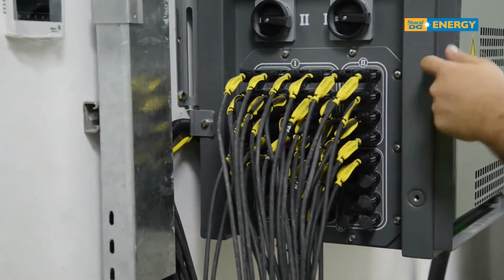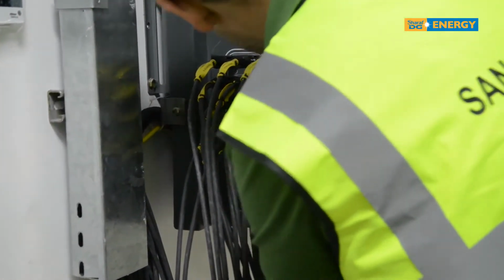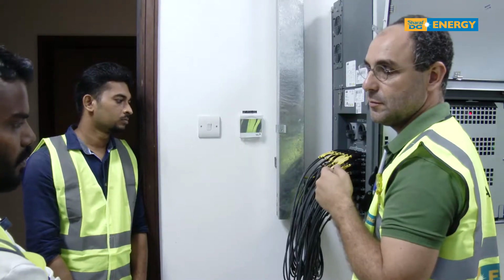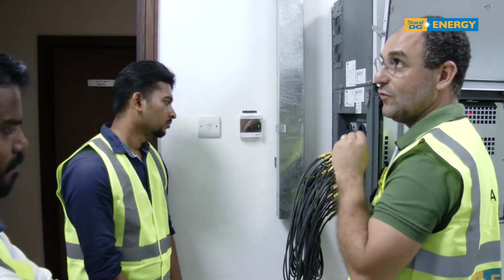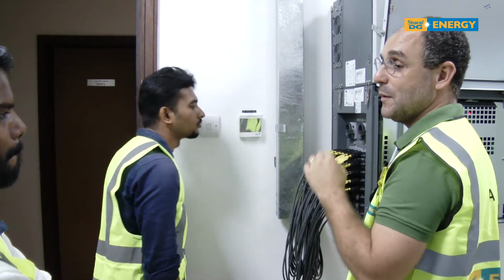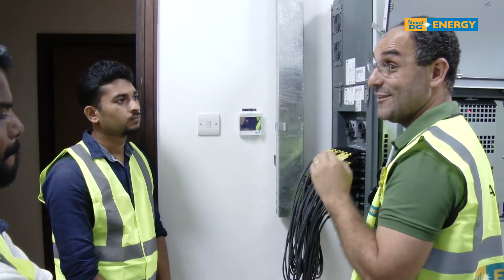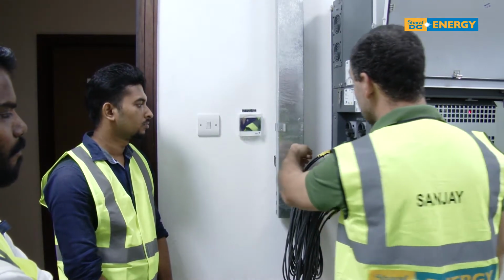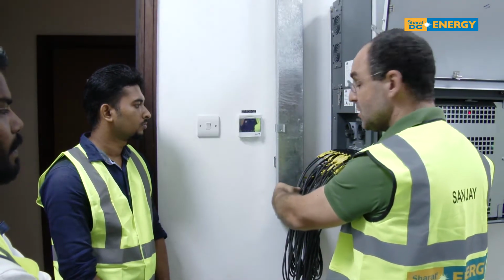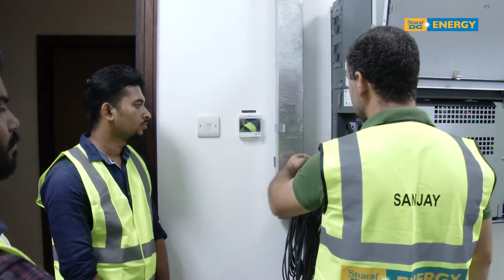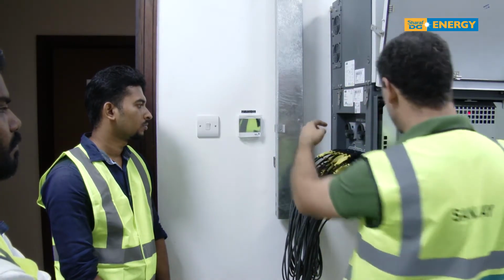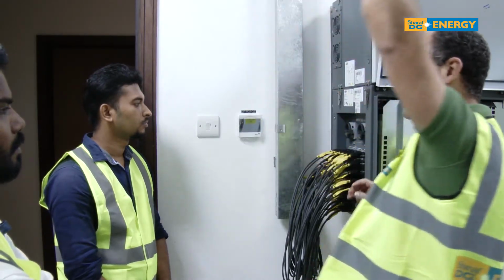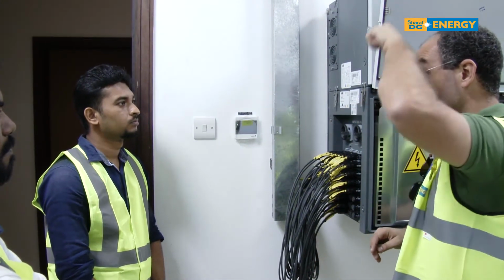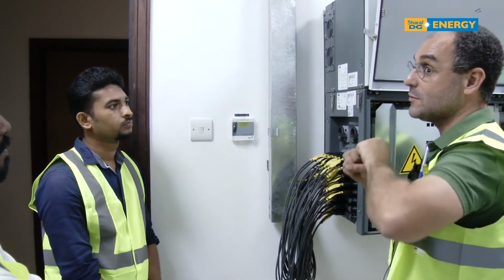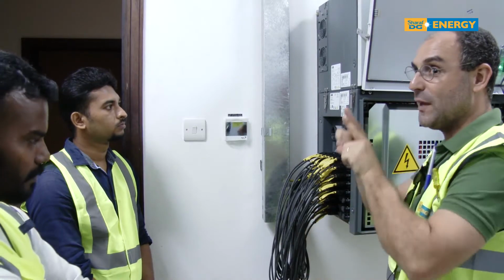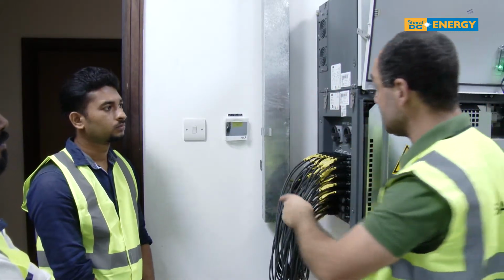If you look at this side, it says do not disconnect under load. So my strongest advice is to always make sure you don't have current circulating. This is the minus, this is the plus. Current arrives here, goes to the bus bar of the DC side and comes back again, so you have a closed circuit. When you have a circuit closed, never open anything. You need to make sure the circuit is open first.